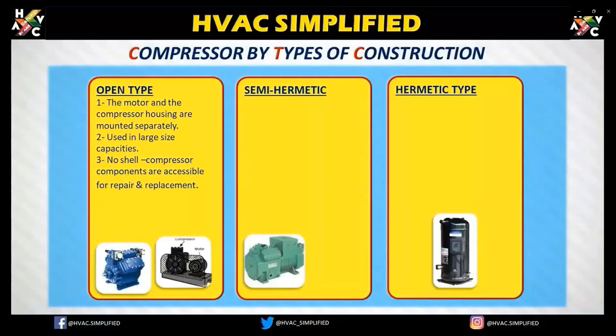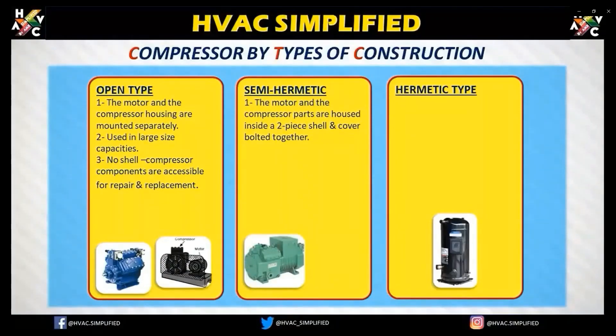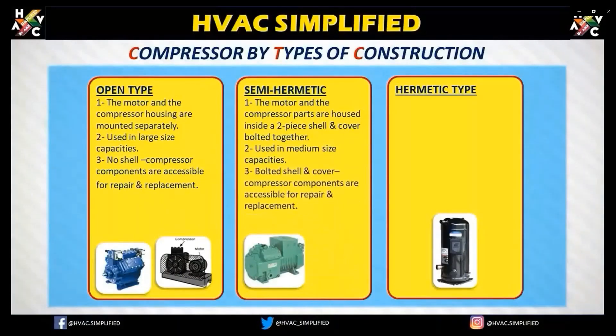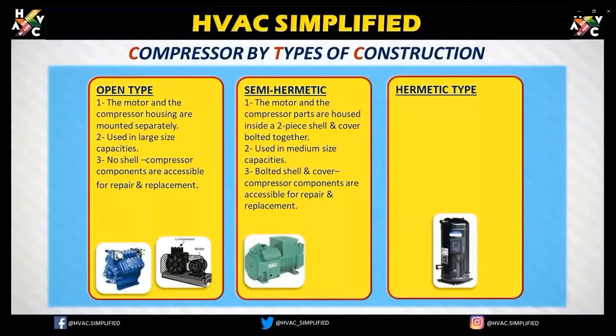In a semi-hermetic compressor, the motor and the compressor parts are housed inside a two-piece shell and cover bolted together, used in medium size capacities. Because the bolted shell and cover design allows access, the compressor components are accessible for repair and replacement. This is a major difference between an open type and a semi-hermetic type compressor.